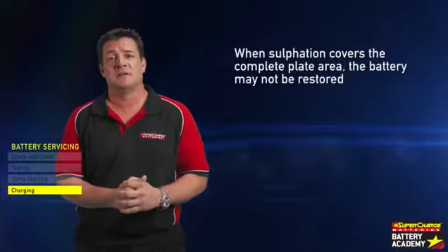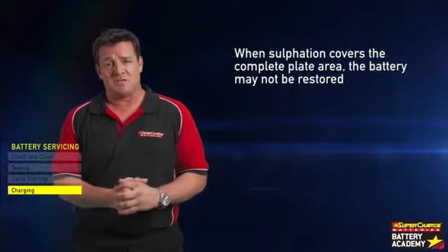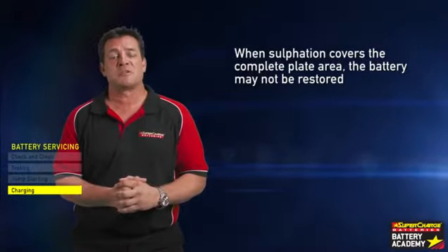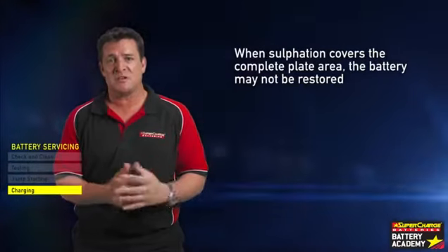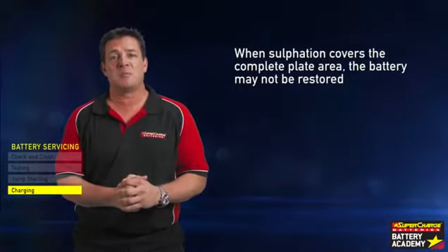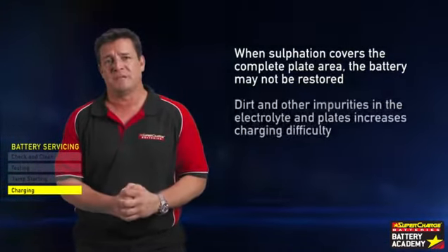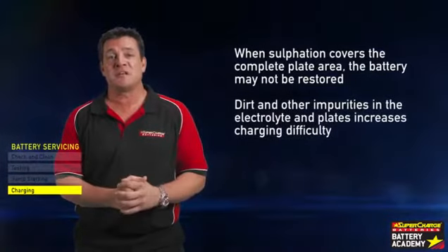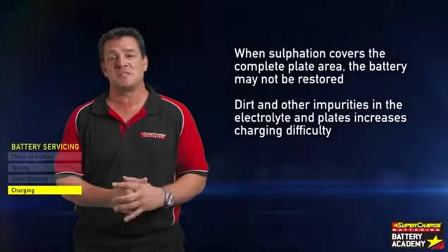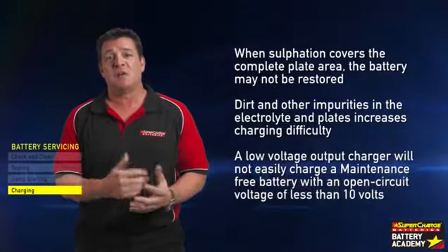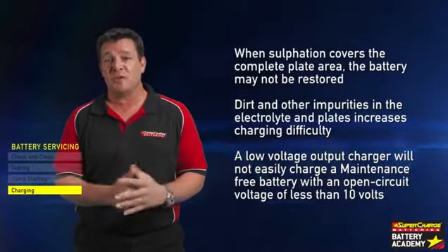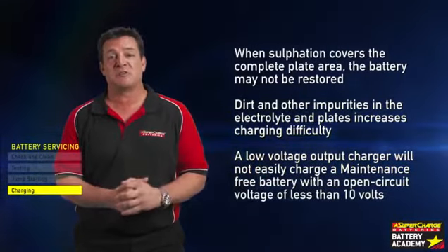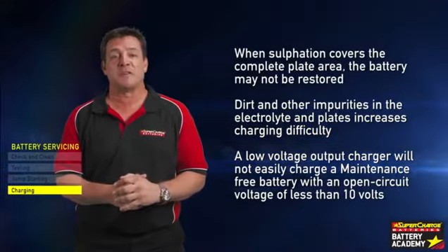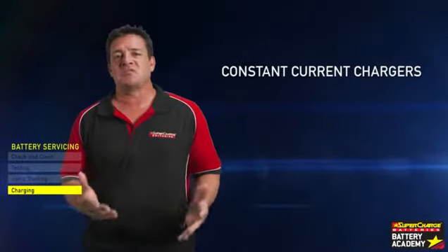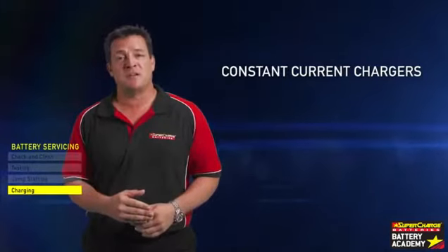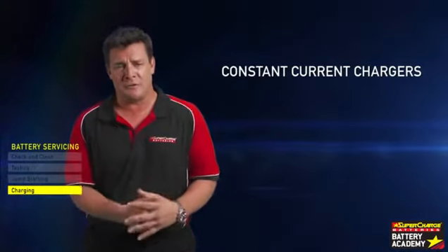State of charge. A battery that is severely discharged will have high sulfate crystals on its plates. When sulfation covers the complete plate area, the battery may not be restored. Dirt and other impurities in the electrolyte and plates increase charging difficulty. A low voltage output charger will not easily charge a maintenance-free battery with an open circuit voltage of less than 10 volts. Constant current chargers charge a battery at a preset or adjusted rate of constant current.